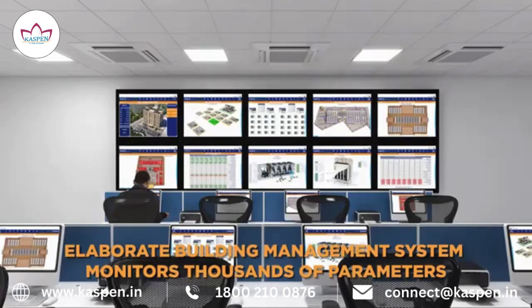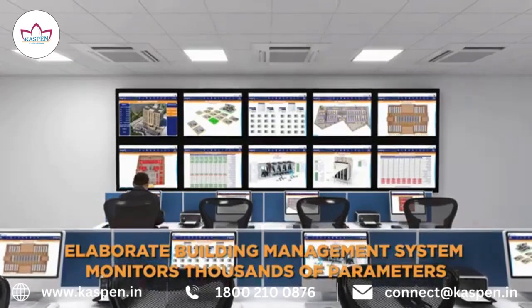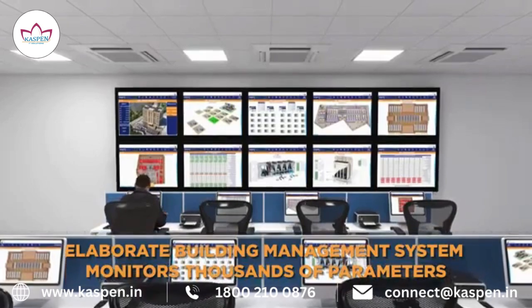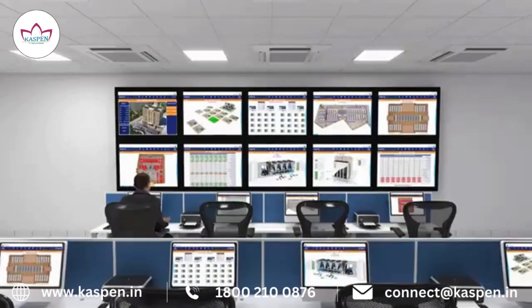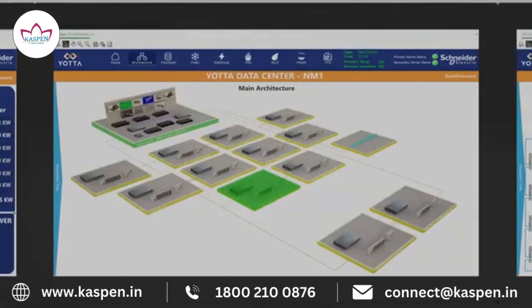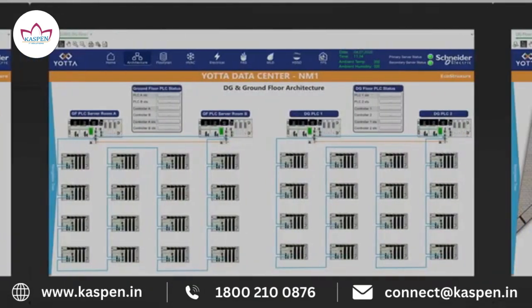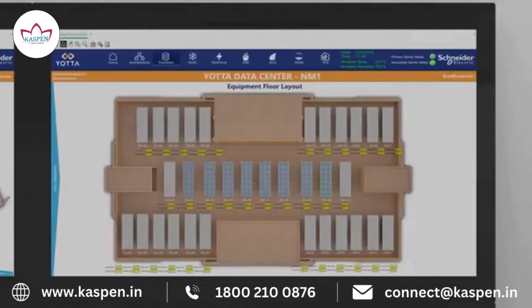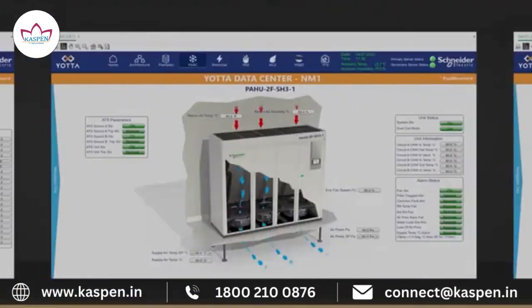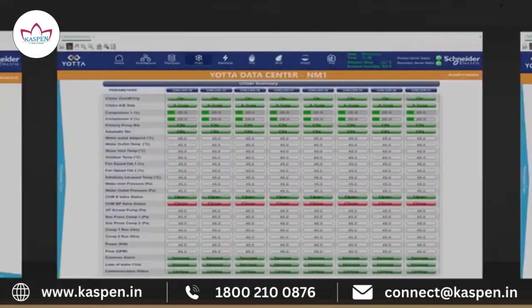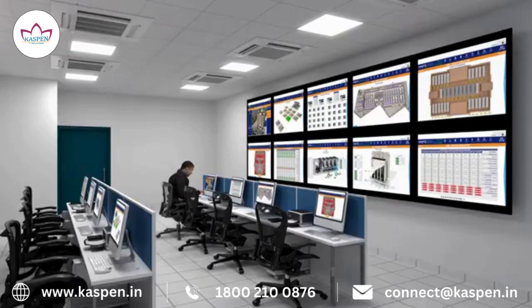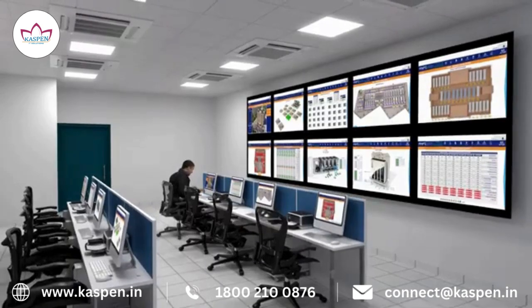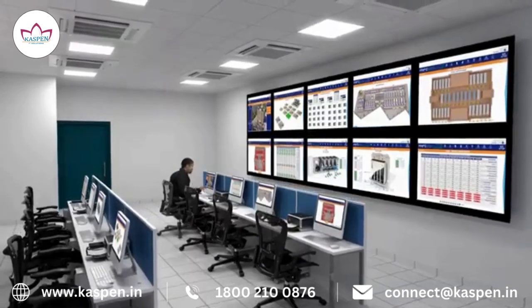A state-of-the-art, feature-rich, and redundant building management system, or BMS, monitors Yotta NM1. Thousands of parameters from every single utility device, including transformers, diesel generator sets, fuel capacity, HT panels, cooling, and power, are monitored by the BMS. Select customers can request for remote BMS logins to monitor their setup in real time.